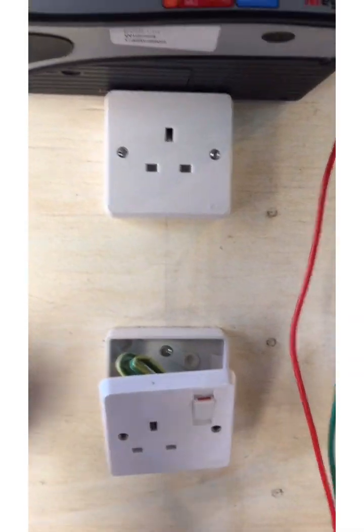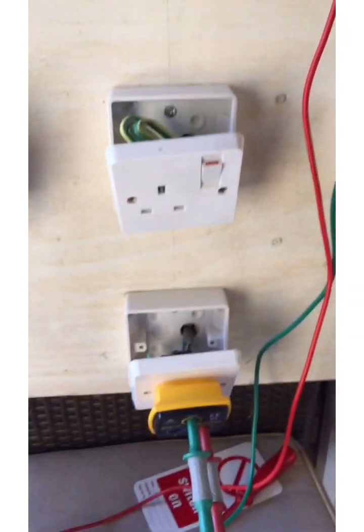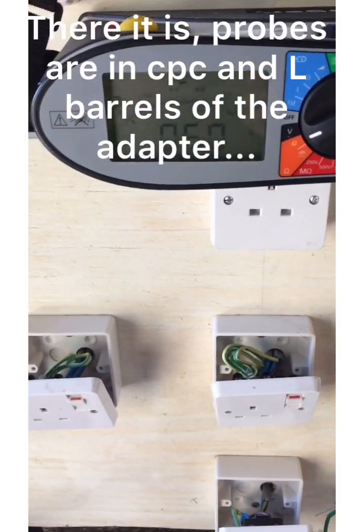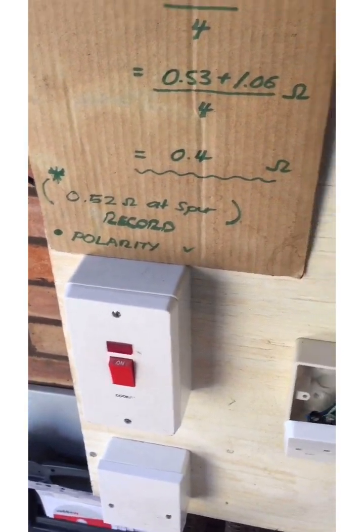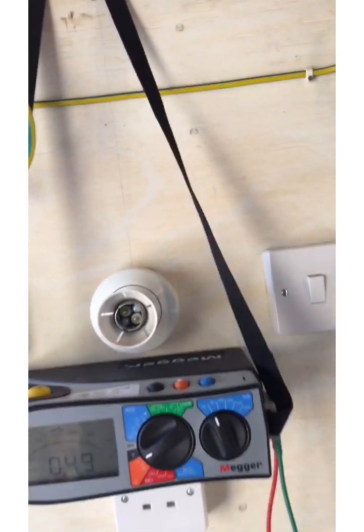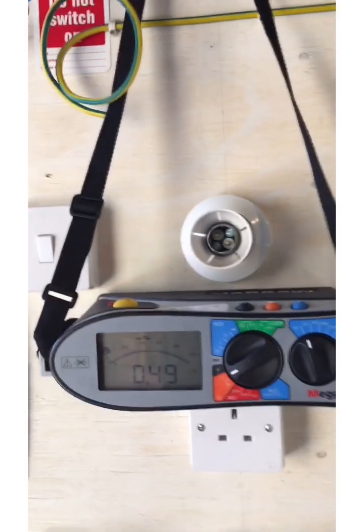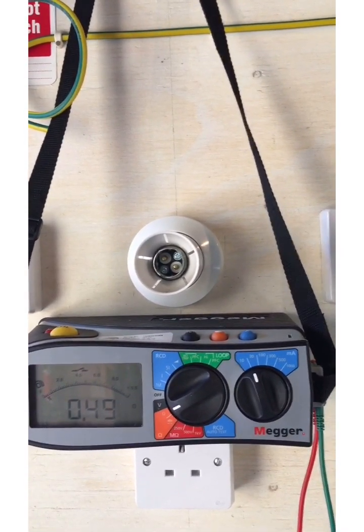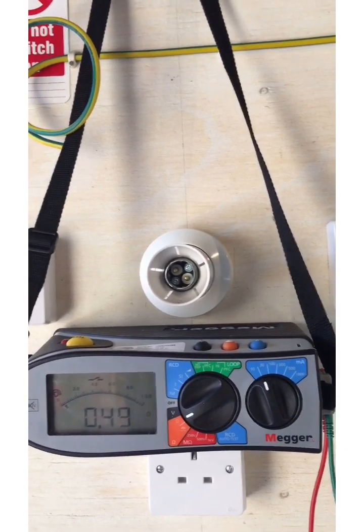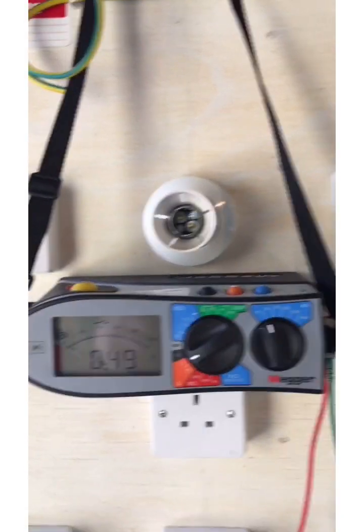0.35 again I'm happy with that and then if we go to the spur and that should give us our highest value and that'll be the one we record and we're getting there 0.5, I got 0.52 before when I did it previously so again I'm happy with that. Now that is our R1 plus R2 value and it also confirms the correct polarity and correct connection of the socket outlets.